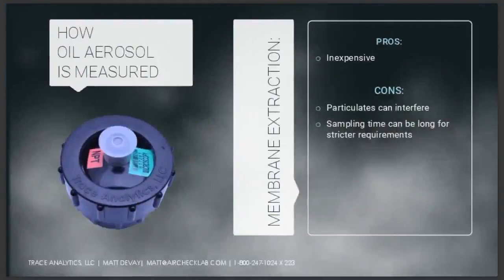All right, on to oil aerosol. So there's a few different ways to collect these as well. Membrane extraction is probably the most common. You've got a membrane media in there, typically some kind of either polymer media or glass fiber. And oil aerosol droplets just collect on it. You pull the filter back out. You either extract it or weigh by difference. You can get as fancy as doing an IR spectra on the extract, and then you know how much oil aerosol is in there. So this one's pretty simple. It's pretty robust. Pretty easy to use, inexpensive, fairly accurate.